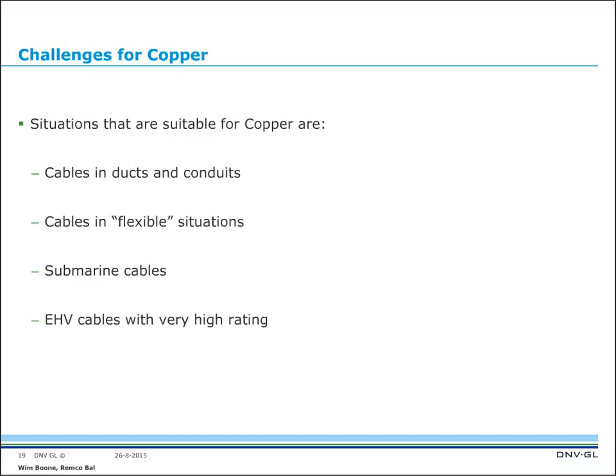What challenges for copper can be mentioned? Situations that are suitable for copper are cables in ducts and conduits, cables in flexible situations, submarine cables, and extra high voltage cables with very high rating. To say a few words on ducts and conduits, when a cable has a small radial size, it can be easily installed. And the same is true for the next one. In a substation, where you do not have much space, the cable has to be bent in various directions, and then copper is more flexible. Submarine cables, I come to that later, but we have the impression that a higher weight of a cable is an advantage. And finally, extra high voltage cables with very high rating. Yes, then there is no choice. When you take the highest conductor cross-section possible, then it's almost always copper.